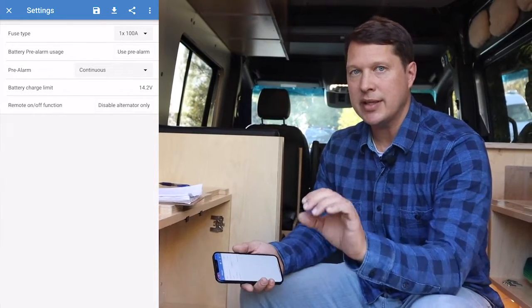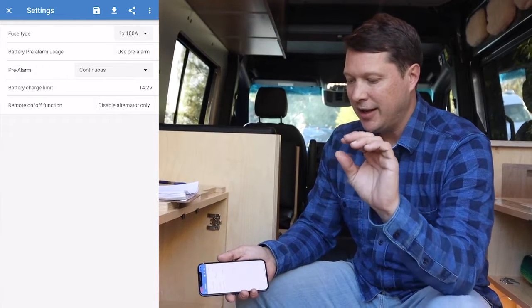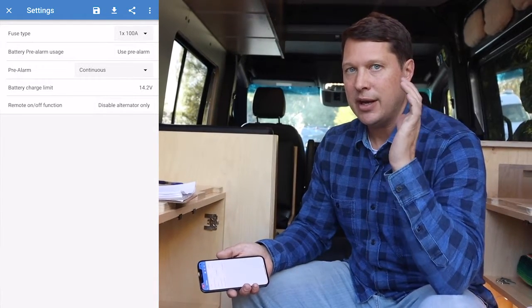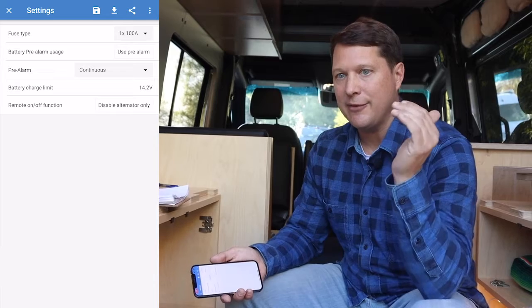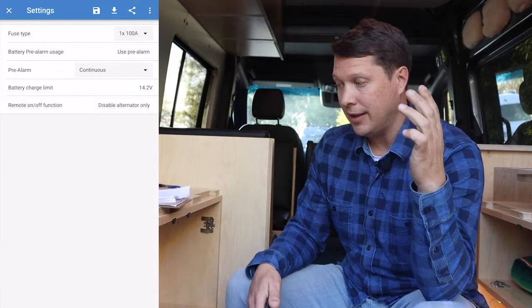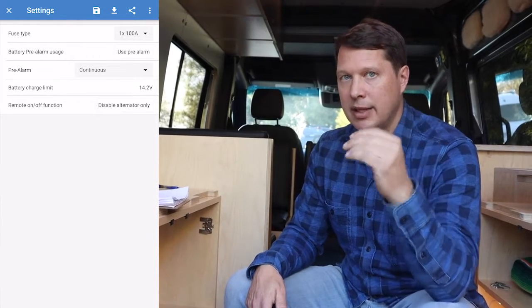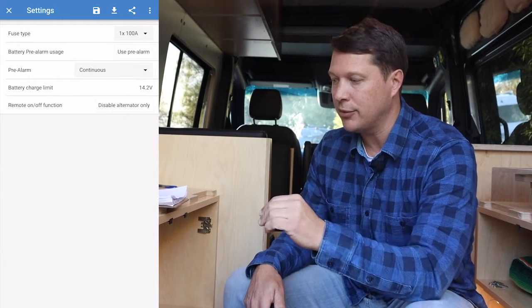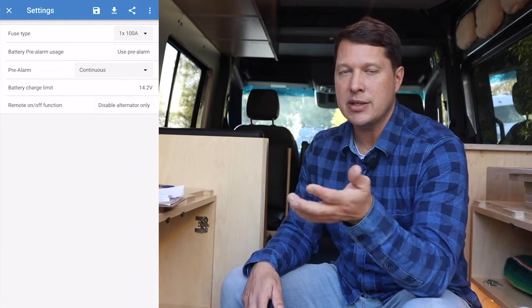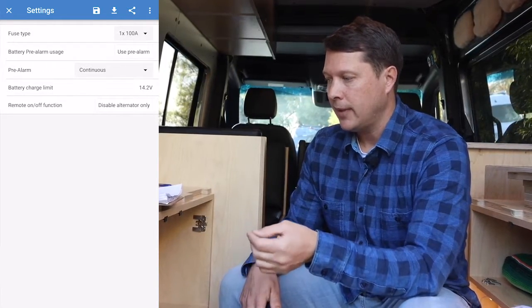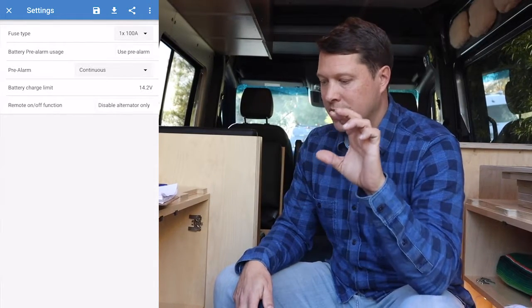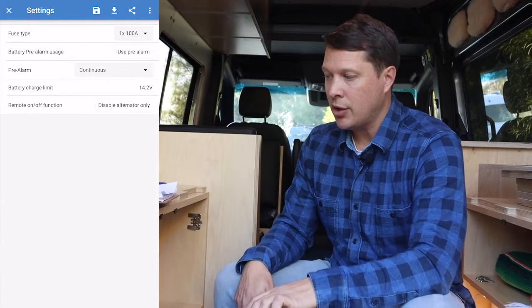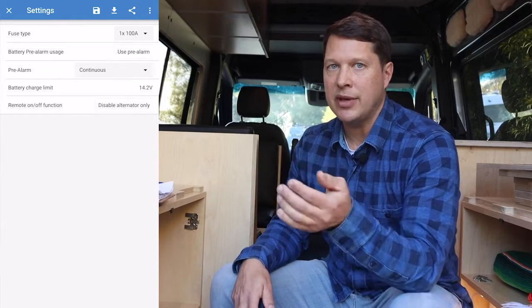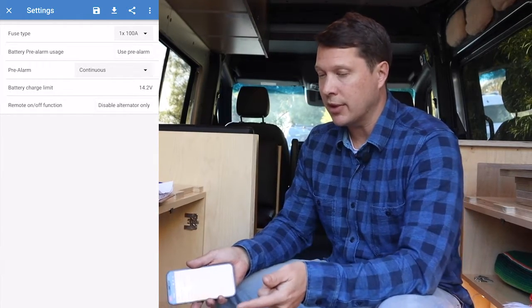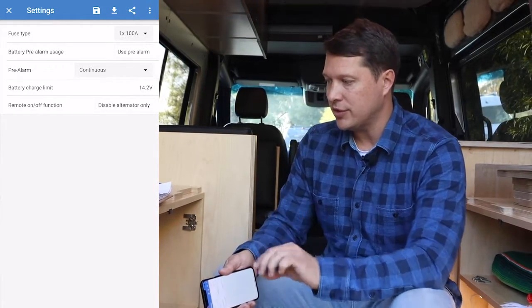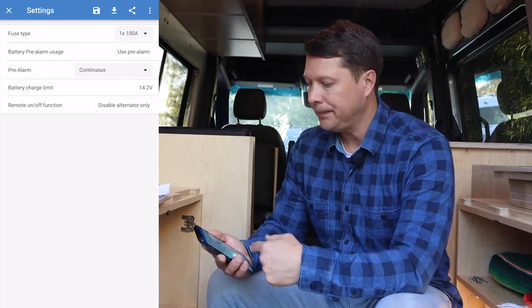So essentially, to make a long story short, if your batteries are very highly charged to a high voltage, there's going to be a lot of impedance in the line, and it will limit down the amount of charge coming through to maybe as little as 15 to 25 amps. In contrast, when the batteries are very low and the impedance is low, that's when you might be getting 70, 80, or even 90 amps coming through the line. So take that into consideration when you size your cable coming from the alternator.